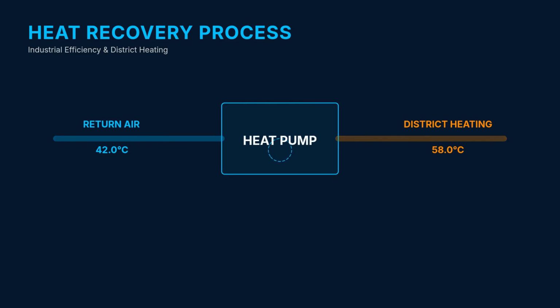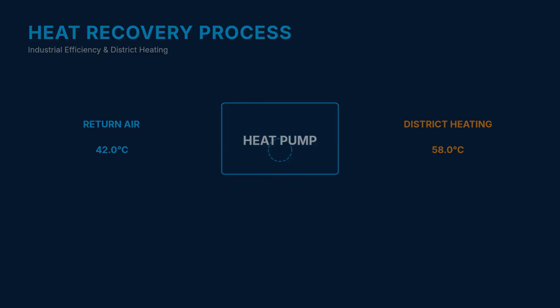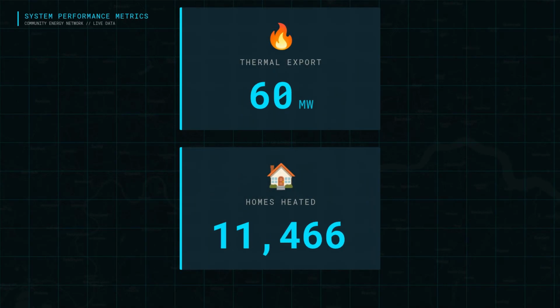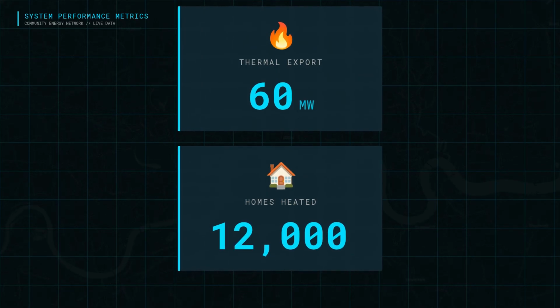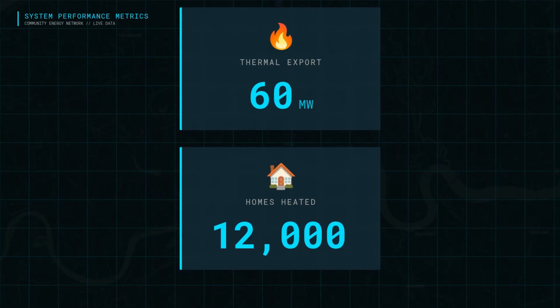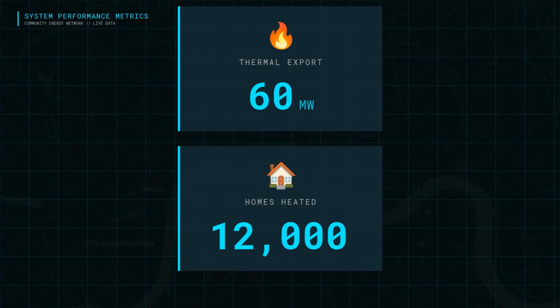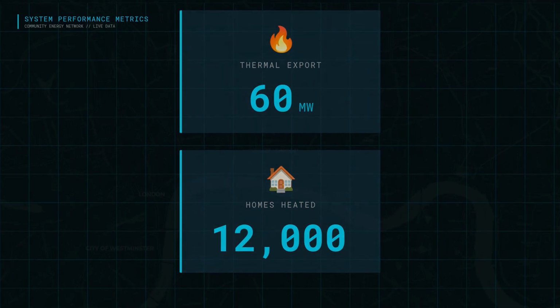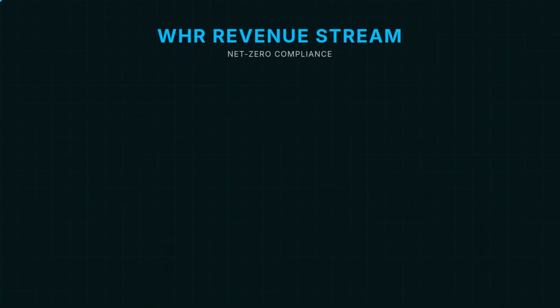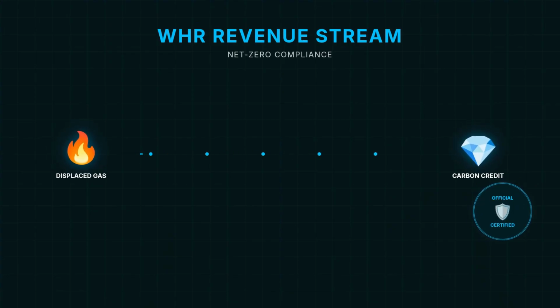High-efficiency heat pumps then lift that temperature to 58 degrees to meet the district heating network's supply requirements for domestic use. At full campus load, we can export up to 60 megawatts of thermal energy. This is enough to provide heating for approximately 12,000 homes, significantly reducing the local community's reliance on individual gas boilers. This displaced gas consumption translates directly into carbon credits. This contributes materially to our net zero obligations and provides an additional bankable revenue stream for the DBFO project.